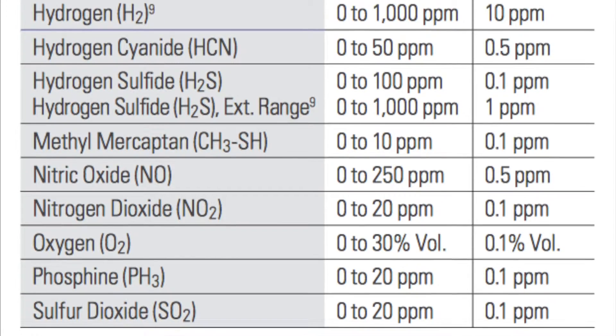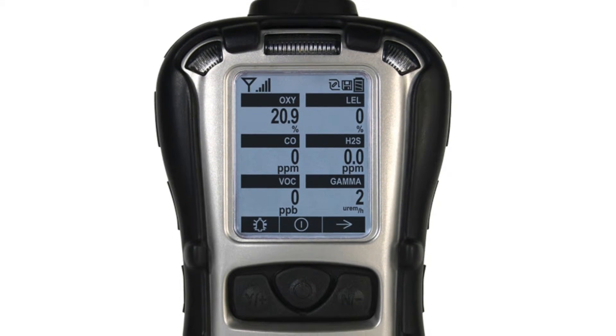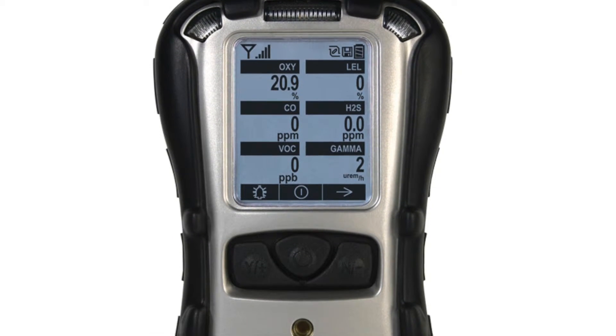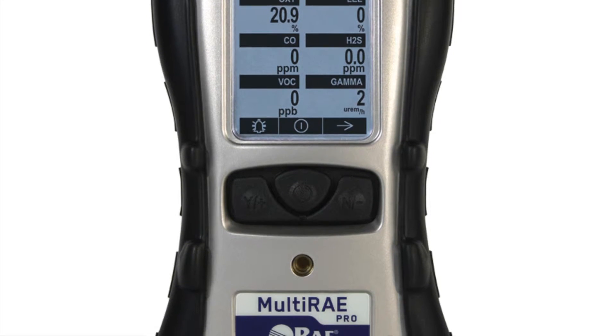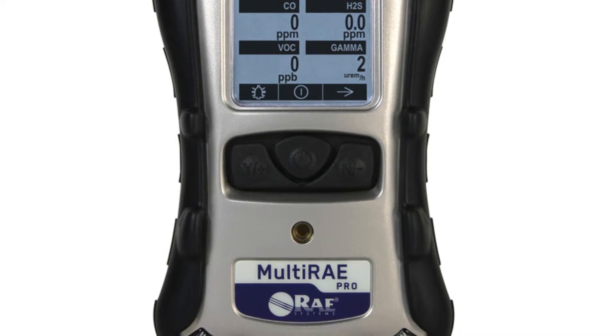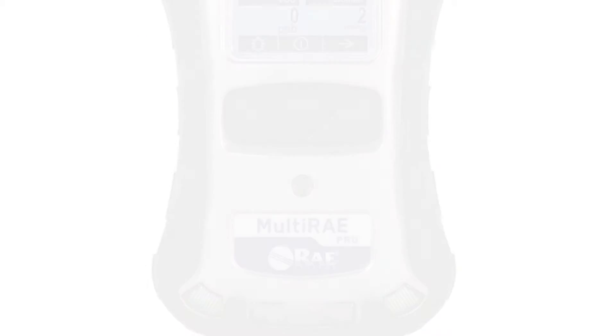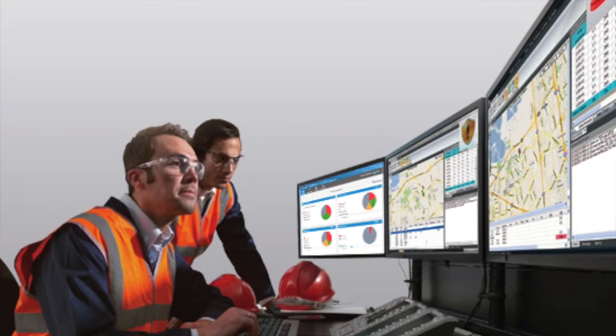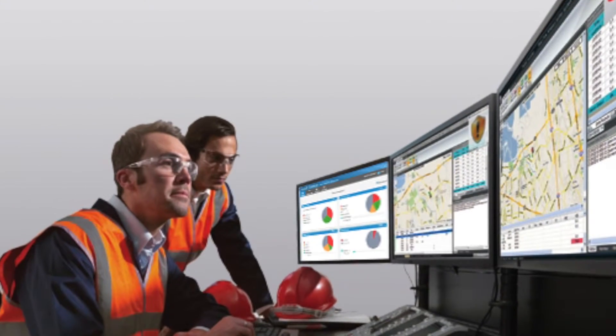The MultiRAE Pro also offers a high-sense PID providing parts per billion measurement capabilities down to 10 ppb, and adds the capability for gamma radiation measurements. All derivatives of the instrument are capable of running wireless options, giving site capabilities to interface with the ProRAE Guardian software.